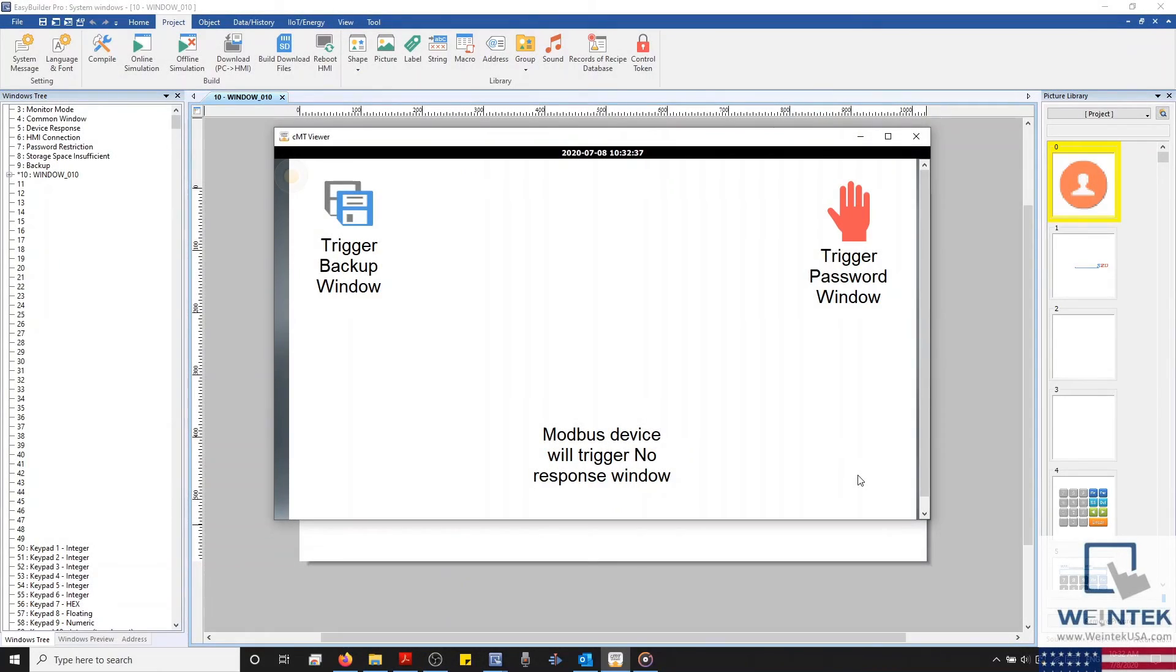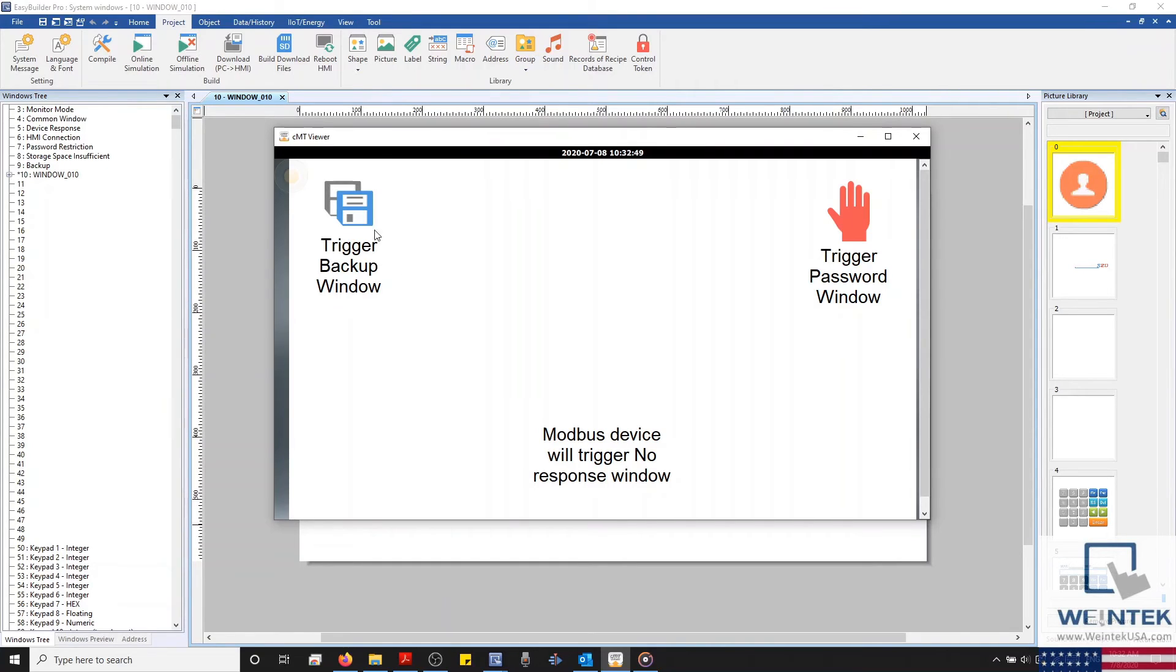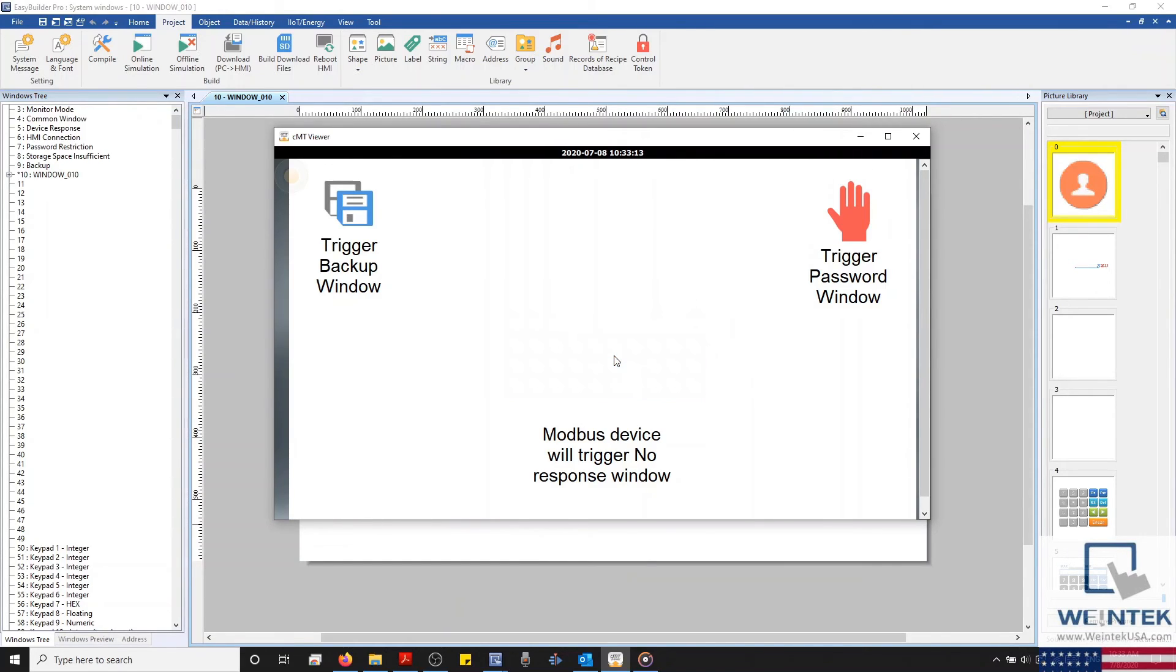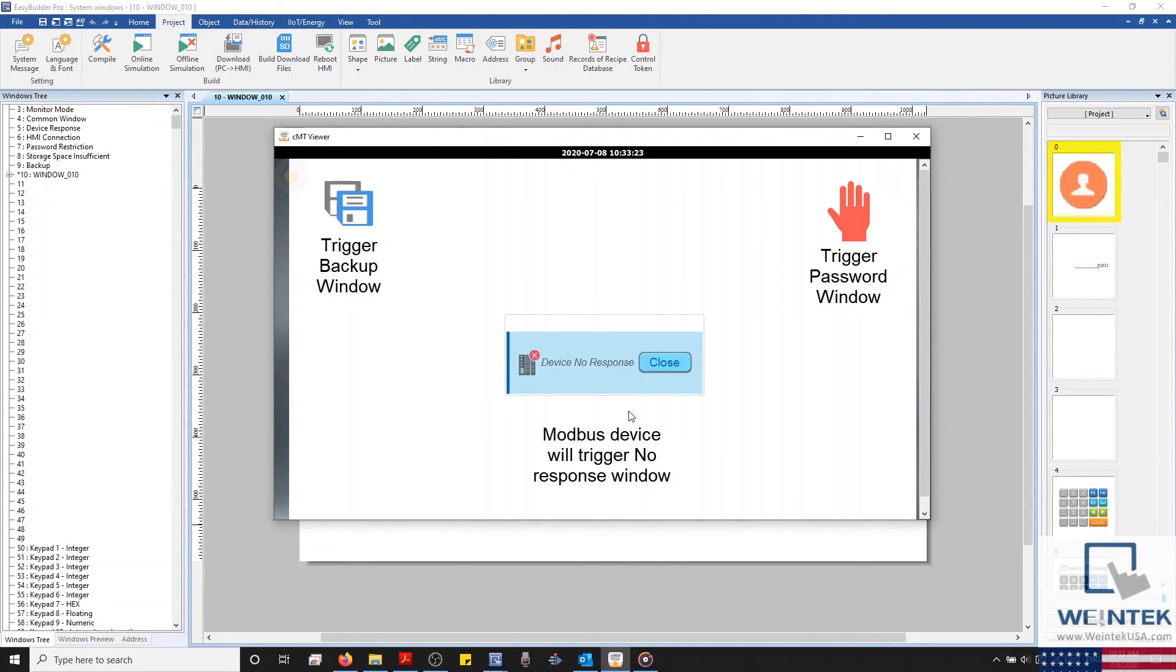Now let's take a look at some of our system windows. On screen, I have a basic demo project that will allow us to display three different system windows. Our Device No Response window, the Backup window, and the Password Restriction window. Let's start off by triggering our Device No Response window. To do this, all I'm going to do is unplug my Ethernet cable. And as you can see, our HMI automatically displays the Device No Response window. The HMI will trigger this window under several different conditions. When the connection is disrupted, as in our example. When the IP address is incorrect. Or if there is a tag issue, referring to our tag-based PLCs, of course, to name a few.